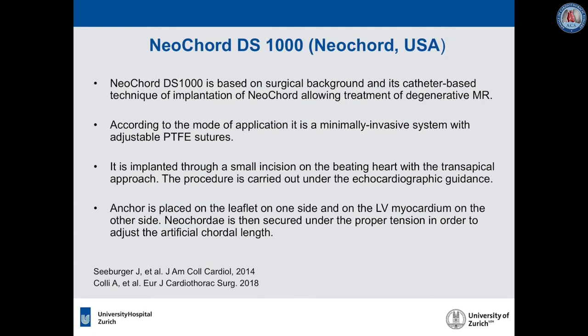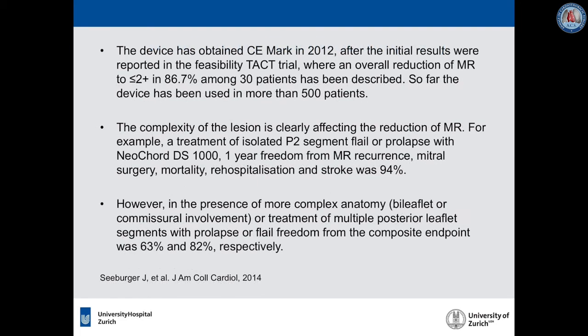The NeoChord DS1000 is based on surgical background and its catheter-based technique allows implantation of neocords for treatment of degenerative MR. It is a minimally invasive system with adjustable PTFE sutures, implanted through a small incision on the beating heart via transapical approach under echocardiographic guidance. An anchor is placed on the leaflet on one side and on the left ventricular myocardium on the other, and the neocord is secured under proper tension. The device obtained CE mark in 2012 after the feasibility trial showed MR reduction to ≤2+ in 86.7% among 30 patients.